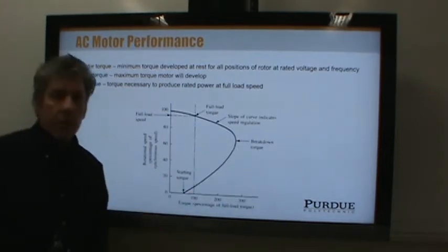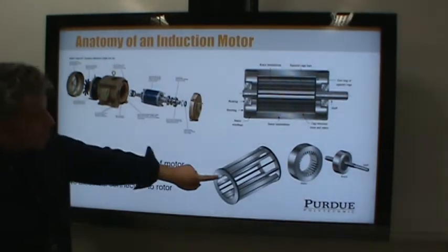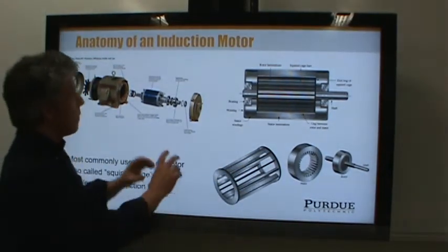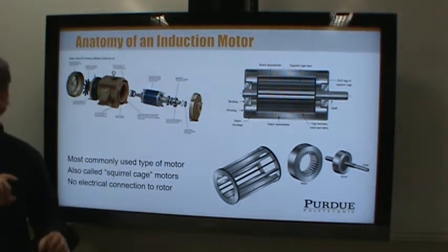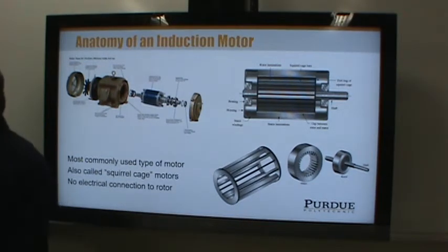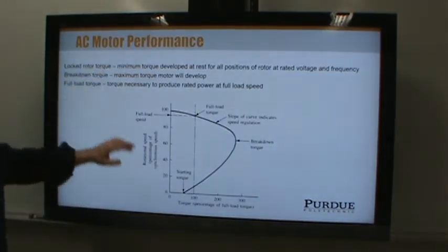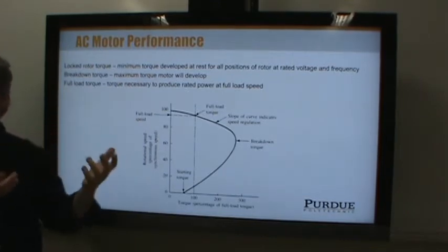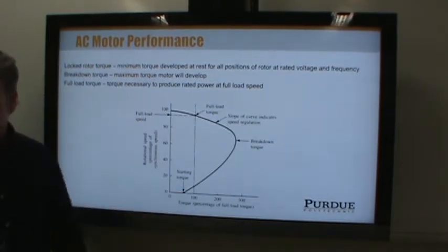Because of the way the motor is made, with current flowing through discrete legs of the squirrel cage, depending on the exact angle of the rotor, you'll develop a different locked rotor torque. It's not a lot of difference, but there is a little. That's why locked rotor torque is defined as the minimum torque — whatever the worst rotor position generates, that's the locked rotor torque.